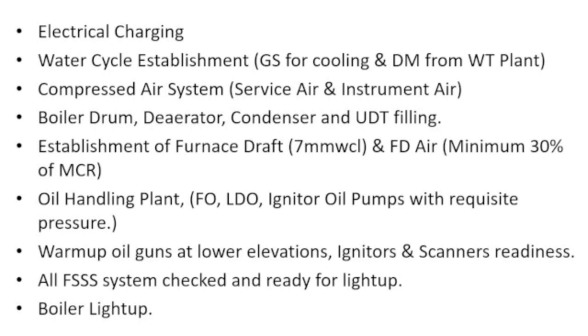Compressed air system, this also we can start once the cooling water is available. Service air and instrument air. The boiler drum, deaerator and condenser and UDT filling with DM water. Establishment of furnace draft, we can start ID fan, FD fan, -7 mm of WCL and FD air minimum 30% of the maximum continuous rating.